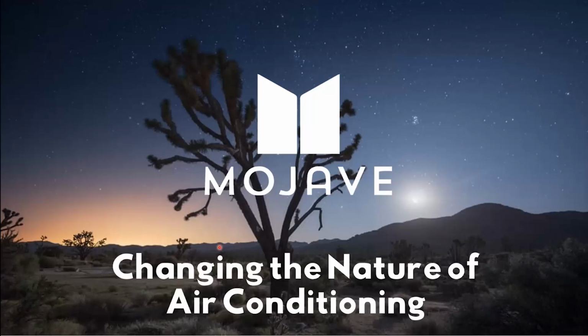To set the stage very briefly, Mojave has a liquid desiccant-based DOAS product. Conceptually, this is an outdoor package-style rooftop product where we pair together liquid desiccant technology with DX technology to create this DOAS product and dehumidification product that's about 50% more efficient than conventional DOAS products and has a much wider range of operation. It has the ability to deliver much lower dew points, if desired, than conventional DOAS products, down into the 40 degree dew point range.